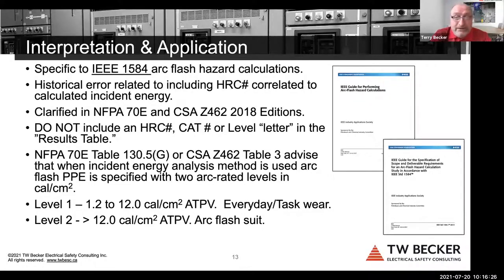So what we did in 70E and Z462 is we added tables after where it mentions determining additional protective measures and two methods. When you have incident energy analysis, you have two arc rated levels, not categories, not level letters, but this is still a problem.